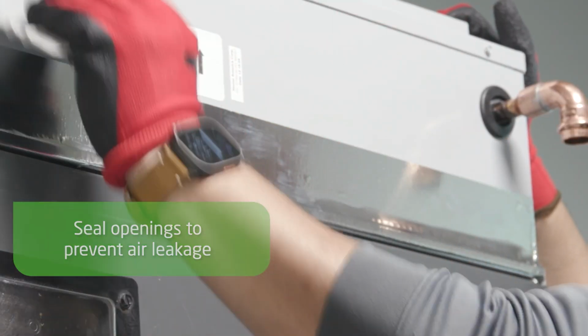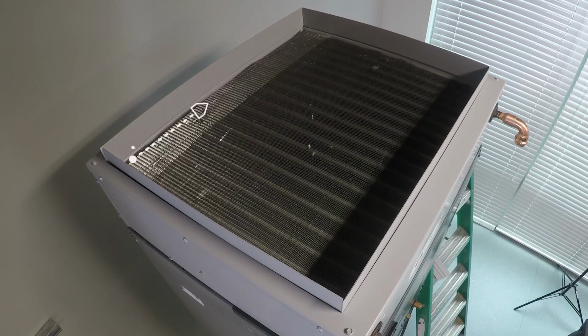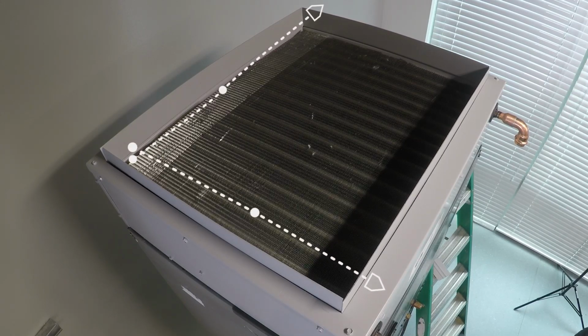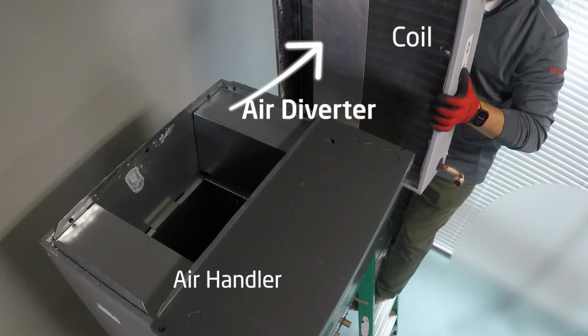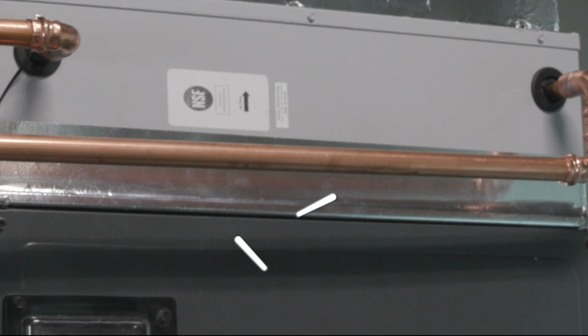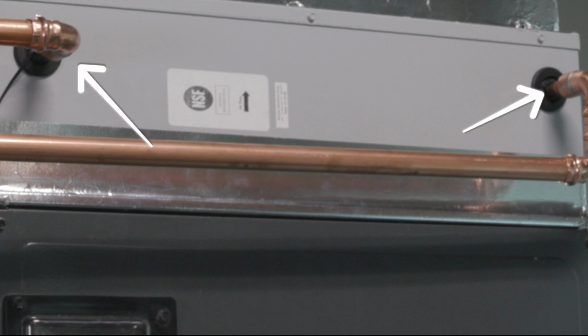The hydronic coil will sit on top of the air handler and fit across the entire length and width of the unit. Make sure to look at the air diverter and the hole on top of the air handler so that it's positioned correctly over the opening. Pro tip: the front of the hydronic coil has the two pipes. That should be facing forward.